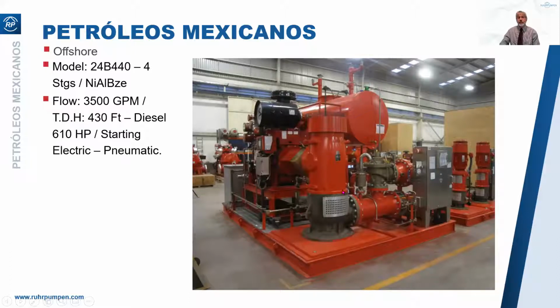Here on this package, I would like to draw attention here. This is the automatic air release valve. Now, on a vertical pump, when it starts up, the column pipe here, you've probably got 100 feet of column pipe, which is empty when it starts. So it's full of air. So you need to release that air before the water can flow through into the system. So an automatic air release valve. And here is a nickel aluminium bronze full flow pressure relief valve.